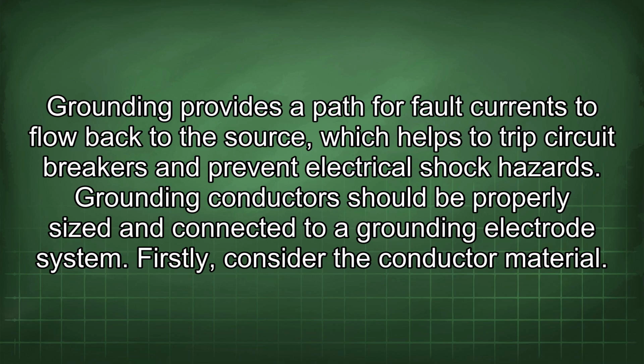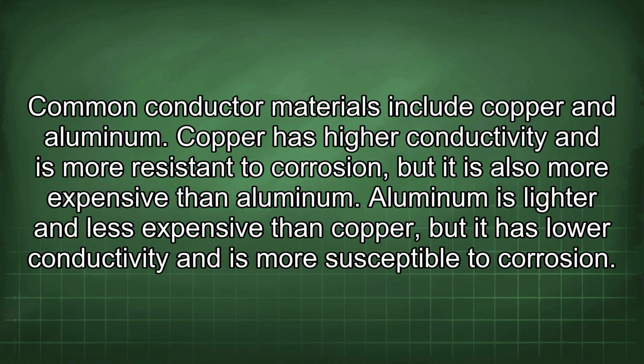Firstly, consider the conductor material. Common conductor materials include copper and aluminum. Copper has higher conductivity and is more resistant to corrosion, but it is also more expensive than aluminum. Aluminum is lighter and less expensive than copper, but it has lower conductivity and is more susceptible to corrosion.